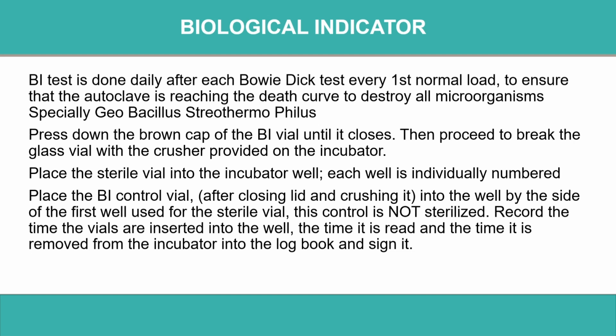Place the biological control vial, after closing the lid and crushing it, into the well by the side of the first well used for the sterile vial. This control is not sterile. Why are we using a control? Because we have to validate the incubator, whether the incubator is working properly or not. So first we use the control to check that there should be a color change, which shows the incubator is working properly and the biological indicator is functional. So we are checking both ways.